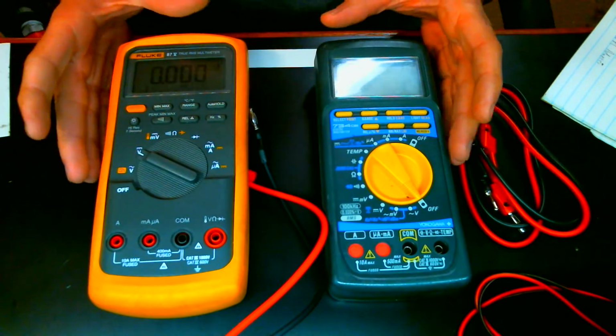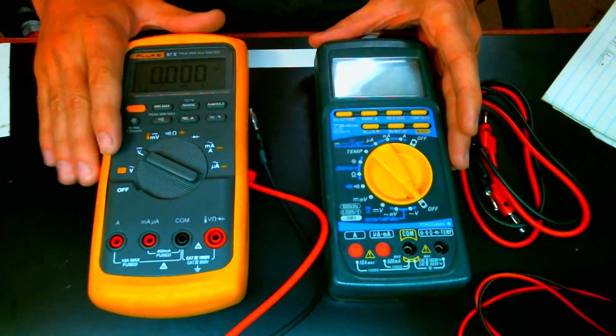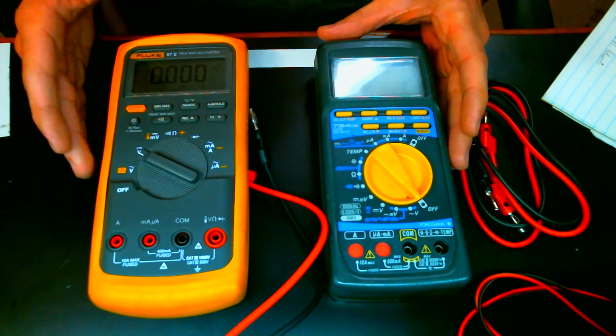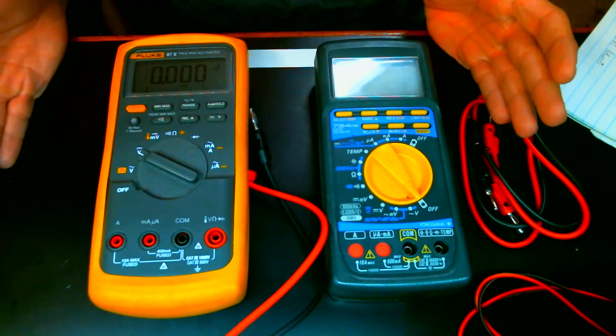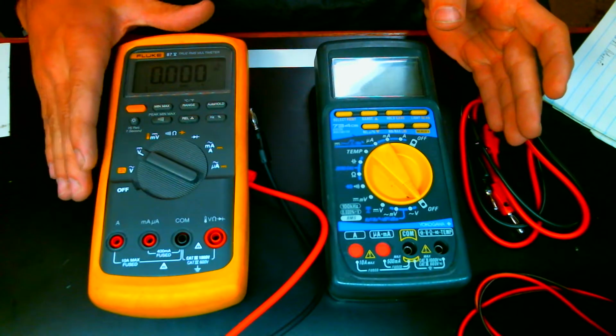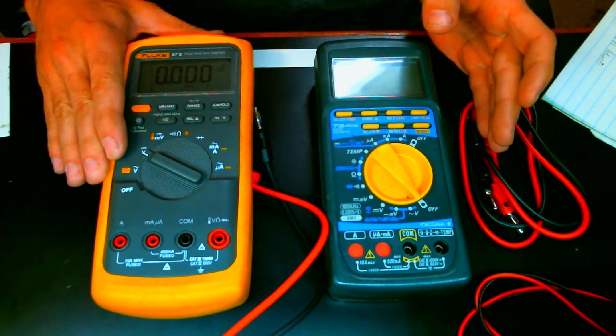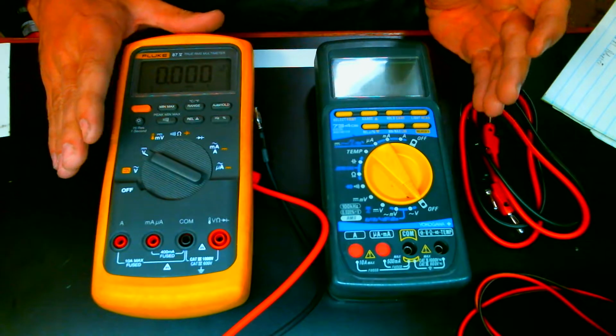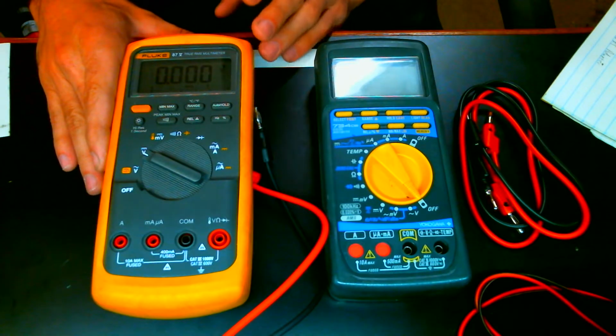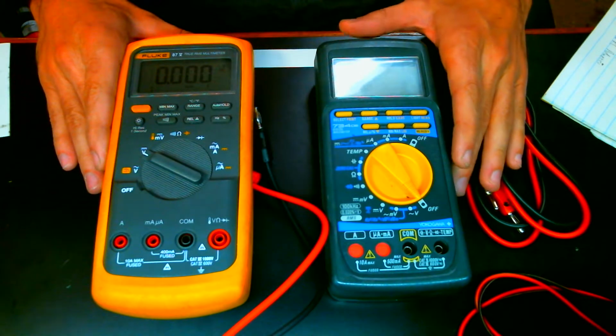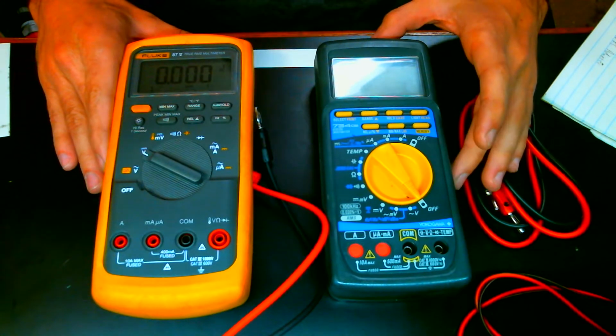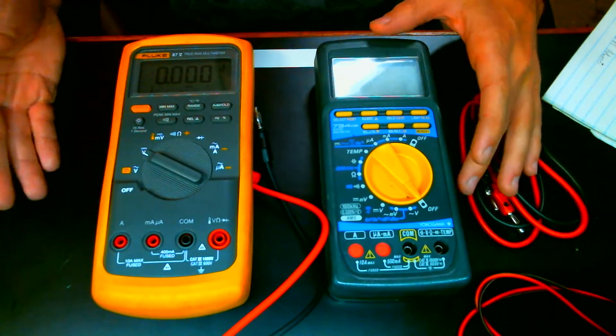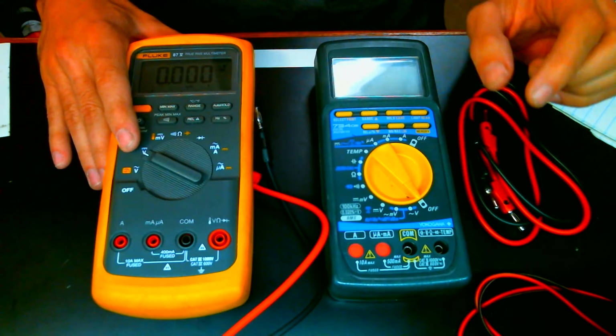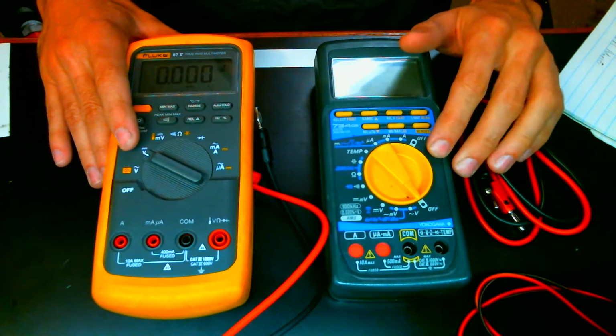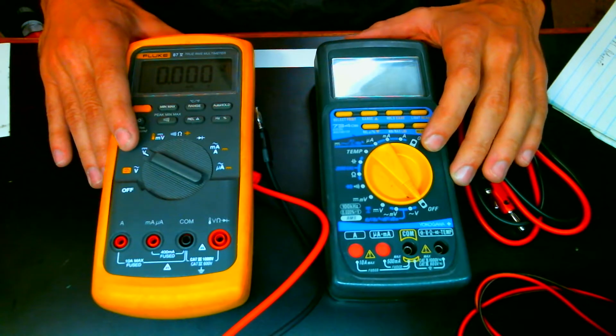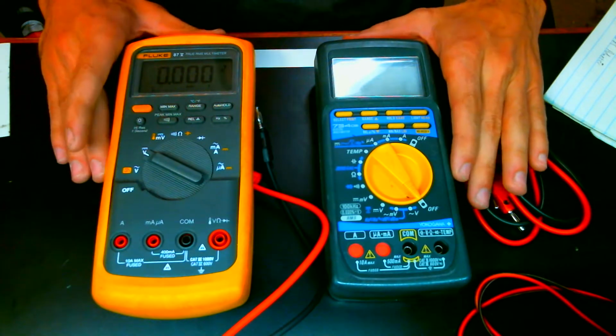And you always want to try to use a reference because I don't use voltage standards, or I don't have any standards of anything really. So I always use a good known meter as a reference, and whenever you're using that reference, you always want it to at least be equal to whatever you're trying to verify.